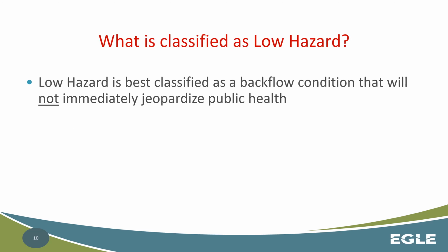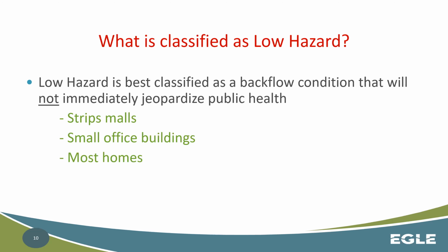What is classified as low hazard? Low hazard, they don't have immediate health impact. They have aesthetic issues. I've said it over and over again, right? Aesthetics. It looks bad. It smells bad. It tastes bad, okay?